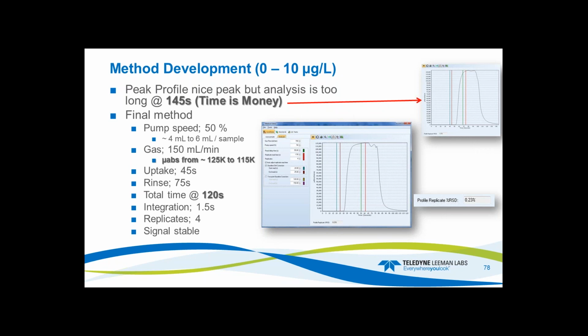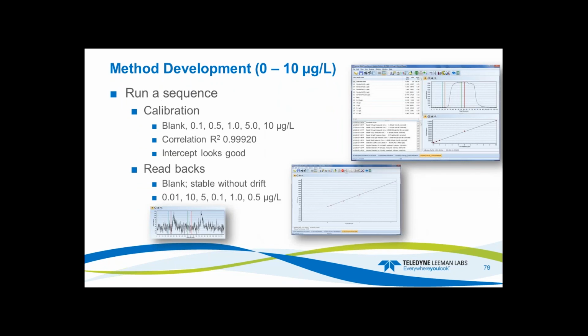My integration I set 1.5 times 4. The signal is very, very stable. So now we're going to run it through very fast, up to 10 for 2 minutes. Again, I do a calibration, correlation, intercept, system looks good. My readbacks go from there, 0.1, 10, 5, and again I like to mix them up a little bit.